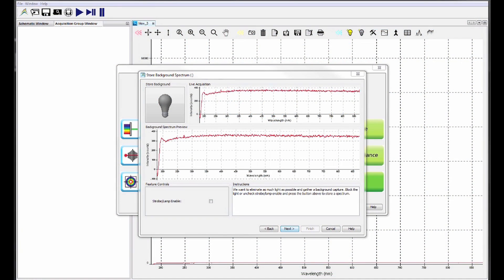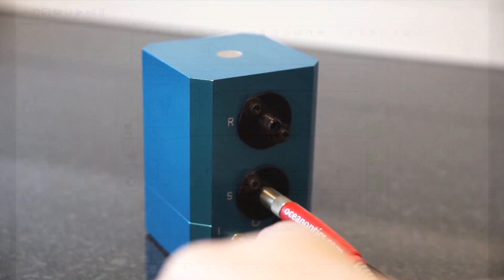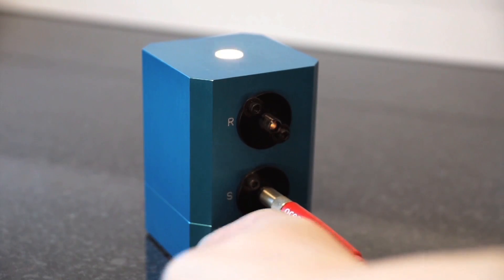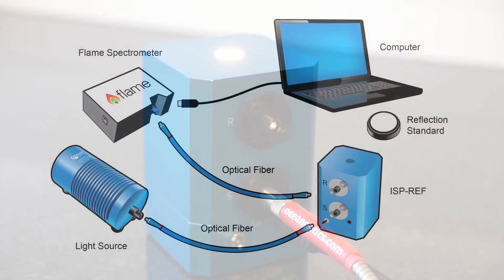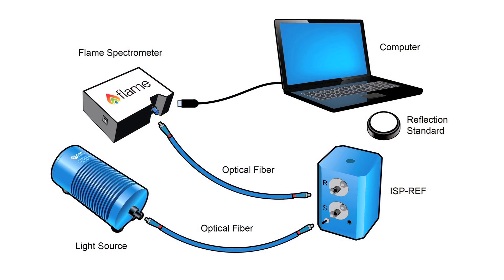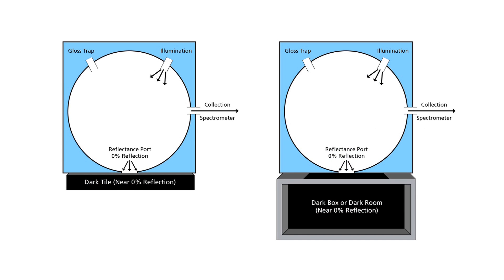When taking your dark measurement, it's very important that you take the dark with the light source on. This is so that your dark measurement takes into account your whole optical system. The objective is to take a measurement with 0% reflection through the reflectance port.